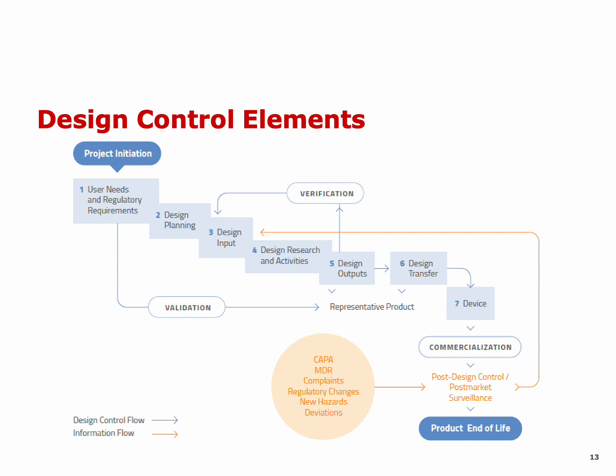We also need to review that manual based on the cases that we receive from the post design controls and post-market surveillance. We will also need to update the user manual for the medical device as well, because again, we may not be aware of all of the risks. We want to stay on the market having a safe product with the efficacy that it needs to be, and with of course the highest quality based on the international standards.